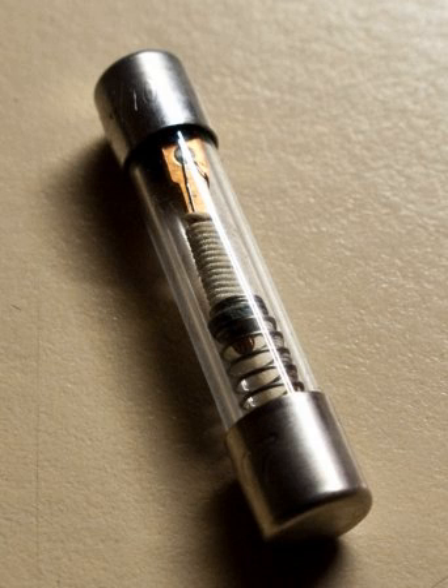There are two styles of fuse base that can be screwed into these units, one designed for rewirable fuse wire carriers and one designed for cartridge fuse carriers. Over the years, MCBs have been made for both styles of base. In both cases, higher-rated carriers had wider pins, so a carrier couldn't be changed for a higher-rated one without also changing the base. Cartridge fuse carriers are also now available for DIN rail enclosures.